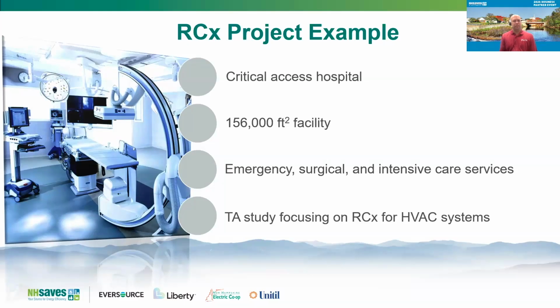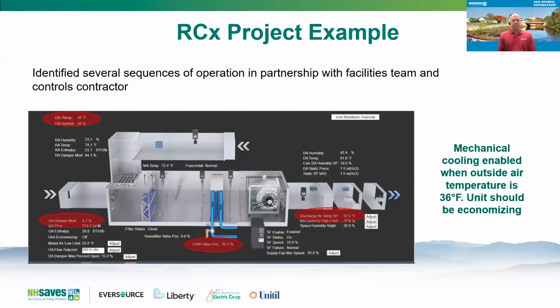So this is a 156,000 square foot critical access hospital, emergency department, surgical, intensive care services, typical hospital. A little smaller of a facility up north, but this was a TA study focused on retrocommissioning for the HVAC system. So one example, again, with the graphics of an air handler, you're going to see here the outside air temperature was 36 degrees, but yet the outside air damper, if I zoom in here, is only 5.7%, while the chill water valve is 35%, delivering a discharge air set point of 62. So a great example of where the economizer sequence is clearly not working properly.